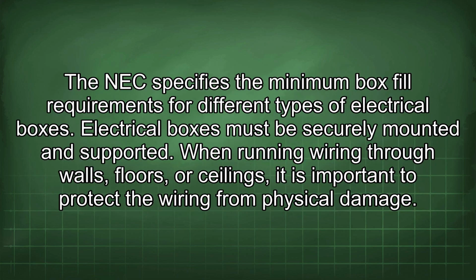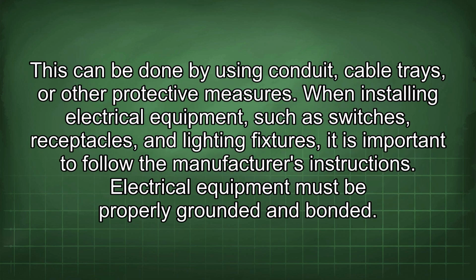The NEC specifies the minimum box fill requirements for different types of electrical boxes. Electrical boxes must be securely mounted and supported. When running wiring through walls, floors, or ceilings, it is important to protect the wiring from physical damage. This can be done by using conduit, cable trays, or other protective measures. When installing electrical equipment, such as switches, receptacles, and lighting fixtures, it is important to follow the manufacturer's instructions. Electrical equipment must be properly grounded and bonded.